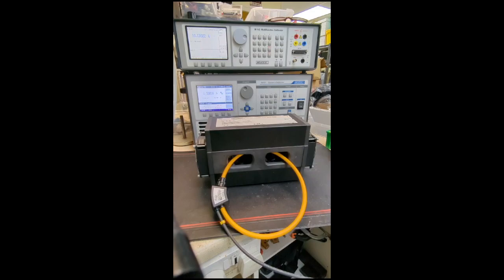And that has several advantages, because with a regular current transformer you need magnetizing current to basically drive the flux back and forth within the core, and clearly that is a source of error right there. Whereas the Rogowski coil does not need magnetizing current to operate. It's sensing magnetic fields, and then it produces quite a low voltage, which is basically integrated and amplified and eventually converted to 0 to 5 amps using our CTA3PH device.